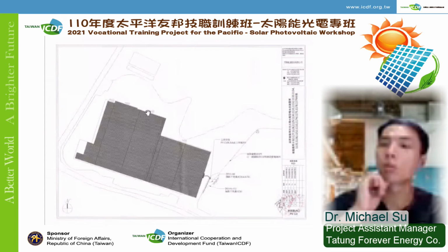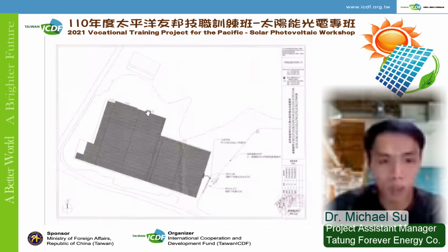Aside from the general arrangement plan, we also provide a simpler elementary diagram. As it is shown, the module of this site is connected to a phase 3 wire transformers which carry 22 kilovolts of electricity. We also have negotiated with TPC about the location of the demarcation point, and it is marked on the top right side of the map. That box-shaped mark is the demarcation point. That is where TPC introduces their cables.